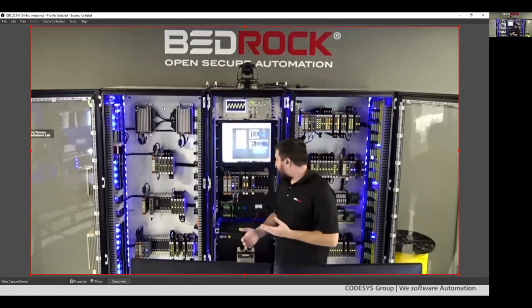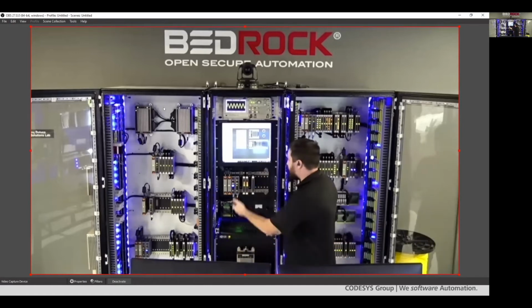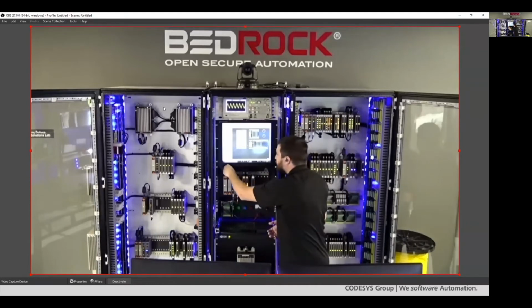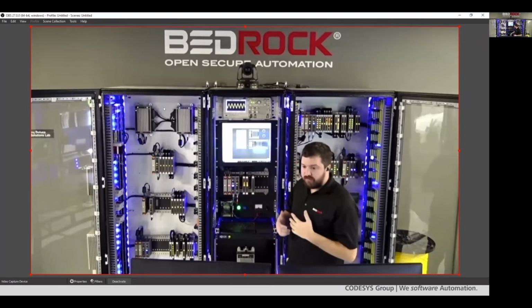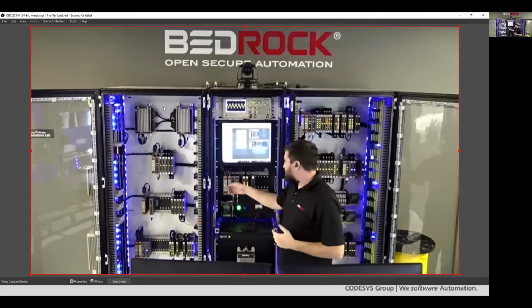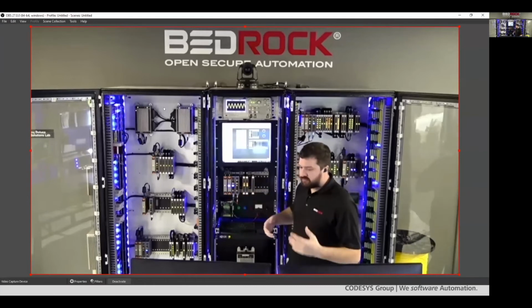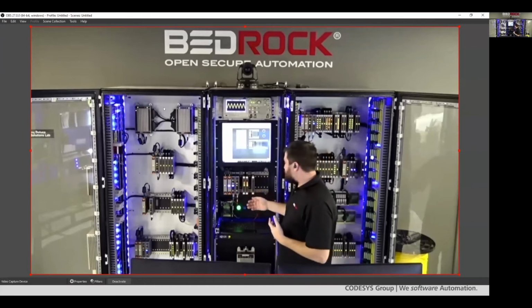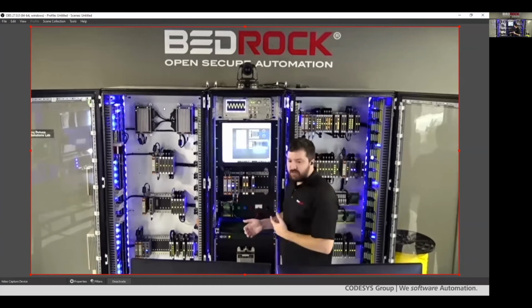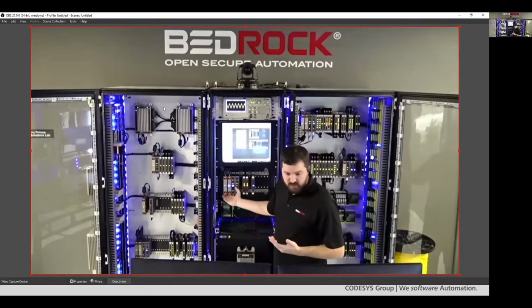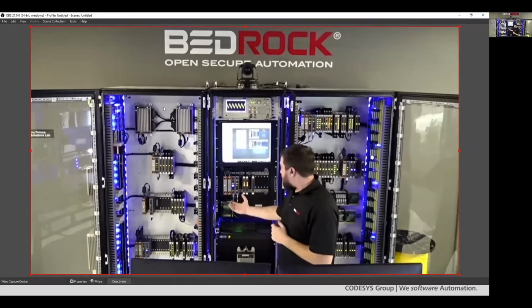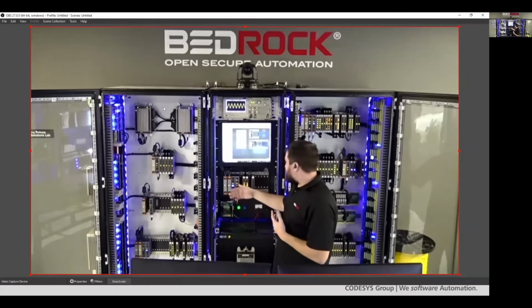And it doesn't matter if you lose power off one of your modules, any module. So that means if you need to do field swaps of controllers, of power modules, of I/O modules, you need to do firmware upgrades of any of the two, you need to change your wiring, change out power supplies. You can temporarily wire in one of these multi-power devices and do that across the board with redundancy.